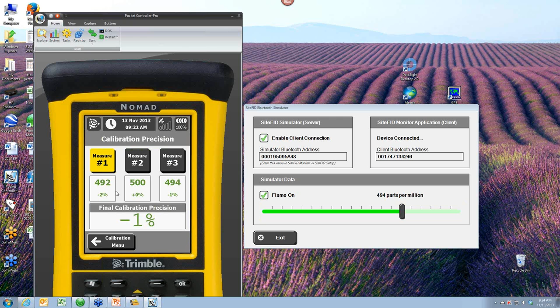So now we're going to go back to our calibration menu. Now we have to do response time, and that is how quickly can we get from 0 ppm to 500 ppm. And remember, we have to do that 3 times again. And so I'm going to go through this very quickly. The first thing we have to do is hit start. Our target is 471, so I'm just going to take my simulator here, hit save. So we did that within 4 seconds.